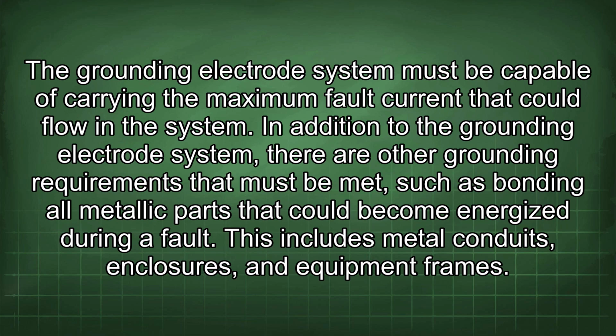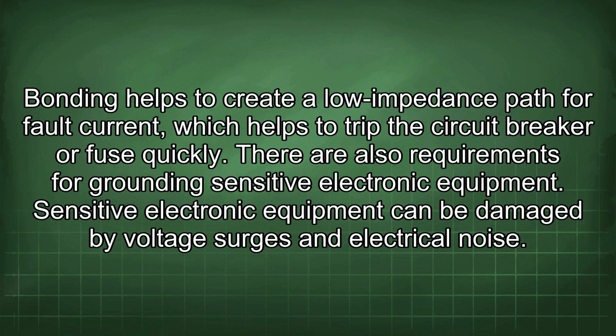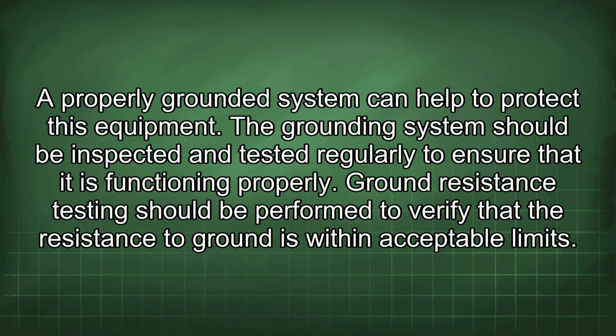In addition to the grounding electrode system, there are other grounding requirements that must be met, such as bonding all metallic parts that could become energized during a fault. This includes metal conduits, enclosures, and equipment frames. Bonding helps to create a low impedance path for fault current, which helps to trip the circuit breaker or fuse quickly. There are also requirements for grounding sensitive electronic equipment. Sensitive electronic equipment can be damaged by voltage surges and electrical noise. A properly grounded system can help to protect this equipment.